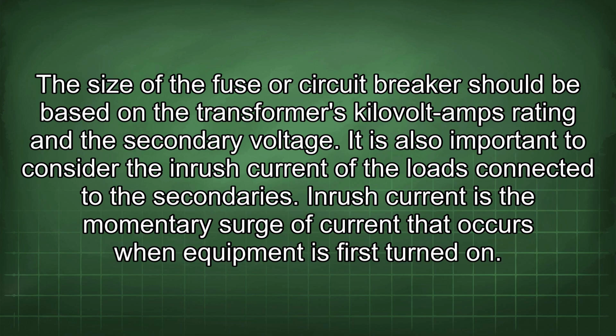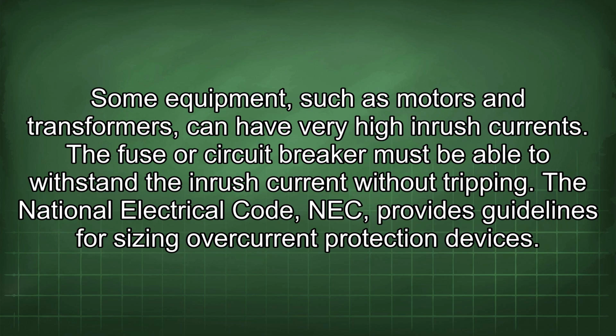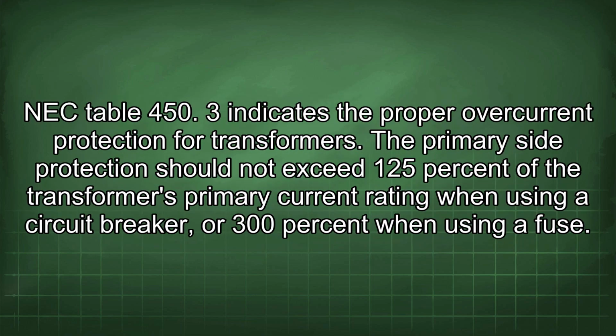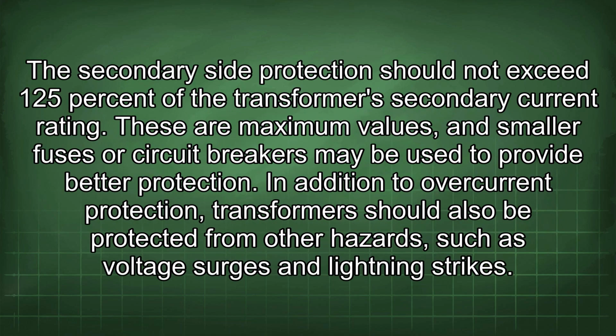Inrush current is the momentary surge of current that occurs when equipment is first turned on. Some equipment, such as motors and transformers, can have very high inrush currents. The fuse or circuit breaker must be able to withstand the inrush current without tripping. The National Electrical Code, NEC, provides guidelines for sizing overcurrent protection devices. NEC Table 450.3 indicates the proper overcurrent protection for transformers. The primary side protection should not exceed 125% of the transformer's primary current rating when using a circuit breaker, or 300% when using a fuse. The secondary side protection should not exceed 125% of the transformer's secondary current rating. These are maximum values, and smaller fuses or circuit breakers may be used to provide better protection.